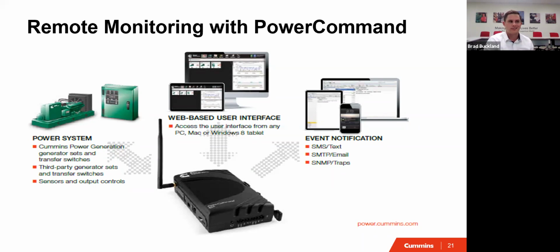I just know our product here, but we have fuel sensors you can put in so you know how much fuel you have, which helps tell you how long you'll be able to last on that generator. It'll tell you some basic output readings and any error messages you're receiving. So if you have a high voltage alarm you don't know what it is, you can easily tell what it is via an app remotely, without having to be on site. You can remotely start your generator to test it if you'd like. It hooks up to your ATS and generator, and you get some more basic information. They all work together to provide a package that lets you not worry about things.